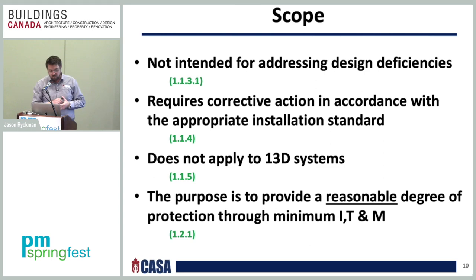Just to continue on with the scope, the NFPA 25 document does not pertain to NFPA 13D systems. That's another installation standard, which we call 13 dwelling, which covers 1 to 2 family dwellings and manufactured homes. Those types of buildings do not fall under the scope of NFPA 25. Okay, it's just to make that clear. So 1 to 2 family dwellings and manufactured homes do not fall under the scope of NFPA 25. Also, I'll keep on reminding everyone that this document provides a reasonable degree of protection through minimum, I repeat, minimum inspection, testing, and maintenance.